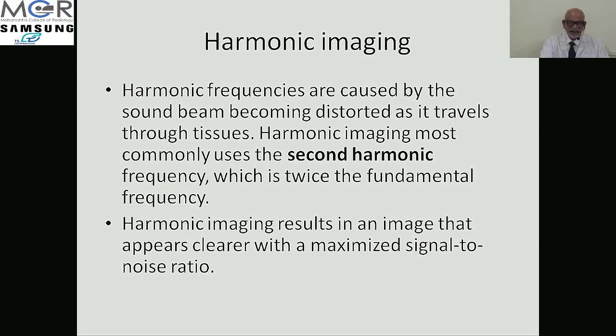And as we all know, the higher the frequency, the better the image quality. So most of the machines can process second harmonic frequencies, and for that you need a broadband transducer which should be able to receive and process both fundamental frequencies and second harmonic frequencies. So in second harmonic imaging, the result is an image that appears clearer, and there is a better signal to noise ratio.